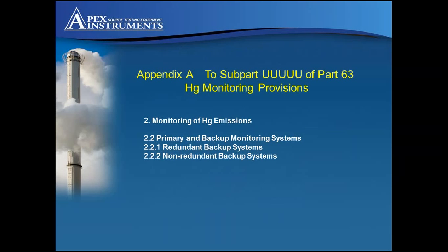Section 2 focuses attention on backup systems, a redundant system located on the same unit or stack on hot standby. But this redundant system must be certified. A non-redundant backup monitoring system is certified at a particular stack or unit, but not permanently mounted at the same sampling location.